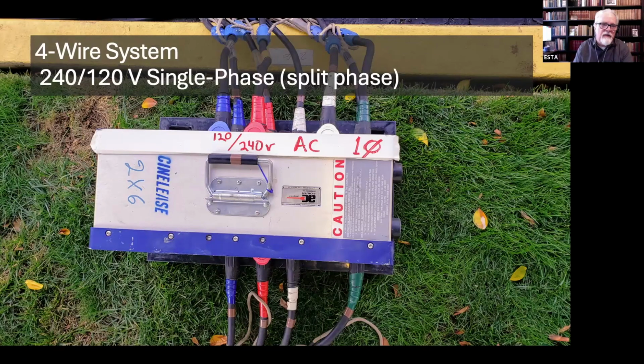Oh yeah, so there's an example of a 120/240 system. I was saying a split phase system. So in this system, the generator actually only produces 2 phase wires, neutral and ground, and the voltage is, instead of 208, it's 240. And some gaffers believe that the voltage helps the performance of HMI ballasts. This was kind of a bigger problem at one stage in the evolution of ballasts than it is now, but it's also much easier to balance loads when you only have 2 phases to balance them between, because anything that's 240 is automatically balanced. But I won't say any more about that unless anyone has questions about it.